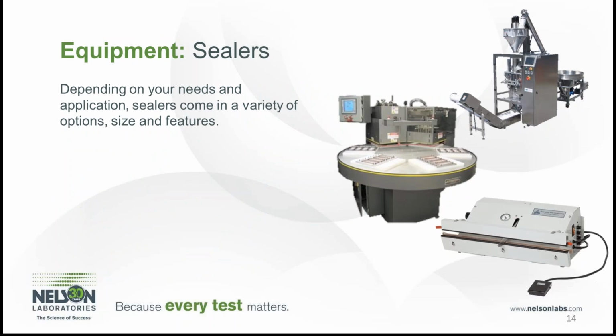Equipment. Sealers are the biggest portion when it comes to package validations and packaging your medical device. Depending on the needs, your application, the size, the end use, there are a variety of sealers, sizes, options, features, functions, etc. that can be purchased for your specific needs. Purchasing a good quality sealer and spending a little bit more time and research up front can significantly reduce issues, loss of time and samples because of insufficient or damaged seals caused by the sealers.